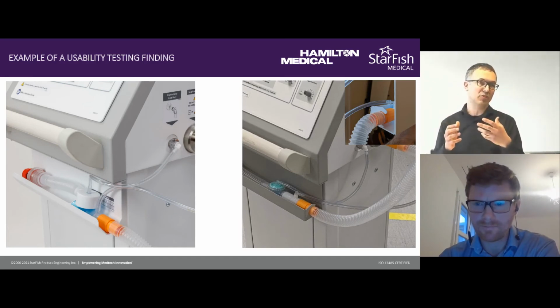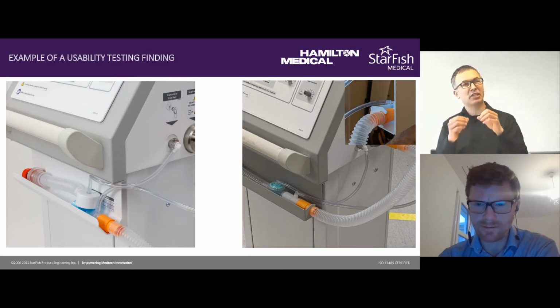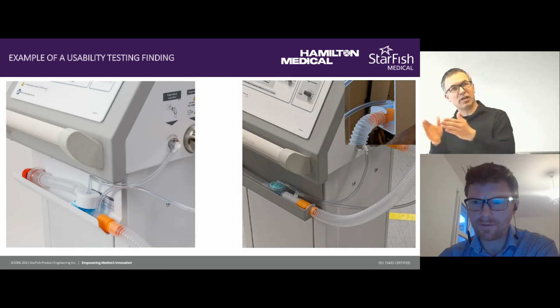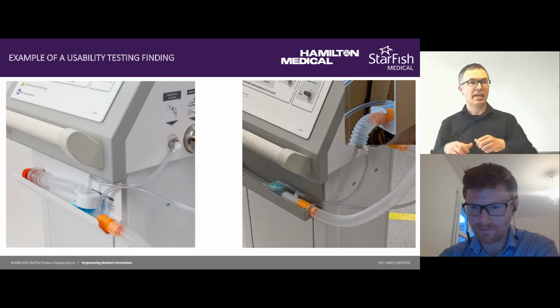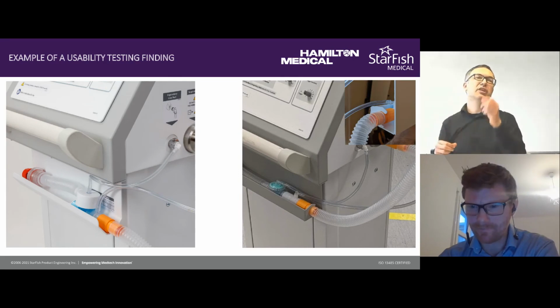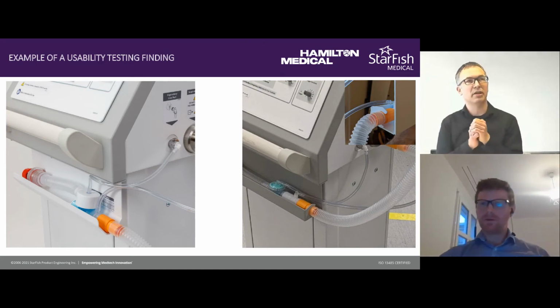But what we discovered during use was that because of the way the machine works, it's always pumping and jerking, so it would slowly ride its way off of the tray. As soon as it dropped, the line would unhook itself, and then the pilot line would be disconnected and the machine would throw a fault, obviously.